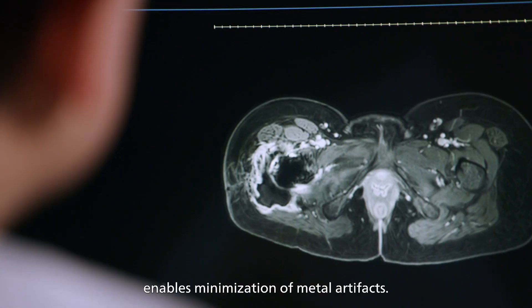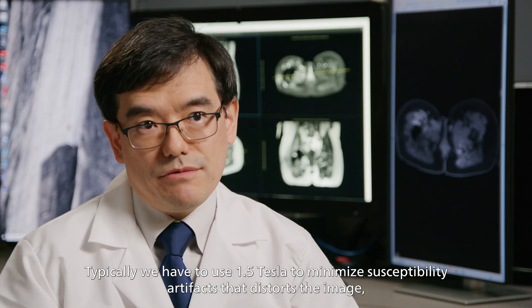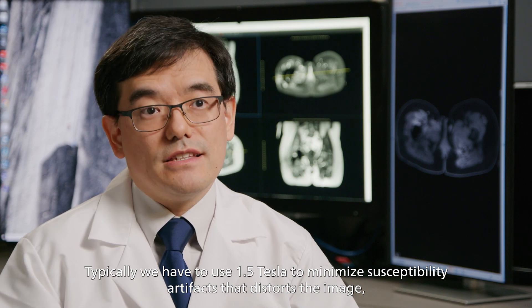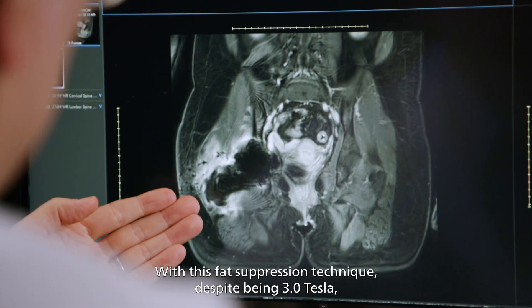The first image I saw with hip replacement totally amazed me. The fat suppression technique this scanner uses enables minimisation of metal artefact. Typically we have to use 1.5 tesla to minimise susceptibility artefact that distorts the image, and that prevents us from looking at the tissues next to the arthroplasty.